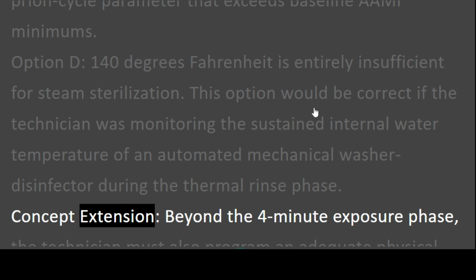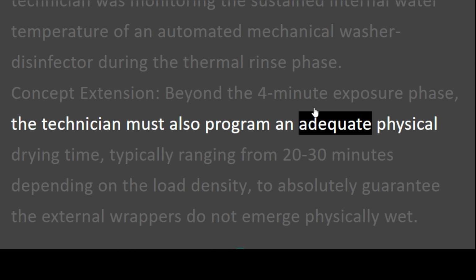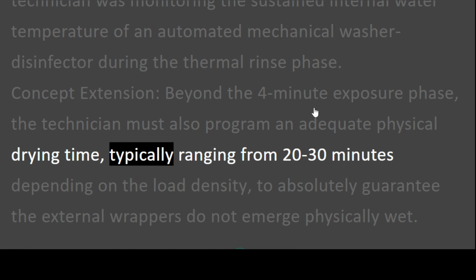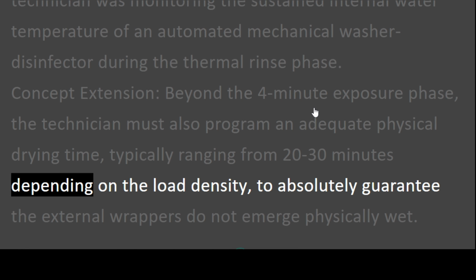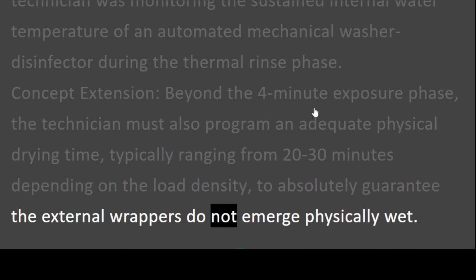Concept extension. Beyond the 4-minute exposure phase, the technician must also program an adequate physical drying time, typically ranging from 20 to 30 minutes depending on the load density, to absolutely guarantee the external wrappers do not emerge physically wet.